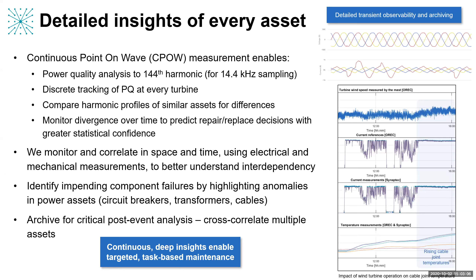It also means that, for example, we can see every interesting or important transient for every asset that we're monitoring. For example, this could be a detailed record of every arcing event that's experienced by a circuit breaker over its lifetime, which is typically a very long lifetime of several decades. So this opens up a new approach to condition monitoring, where finally there's enough data to make intelligent decisions about asset performance over time and maintenance of that asset. Or more realistically, it might be to train a machine learning algorithm to do that automatically.